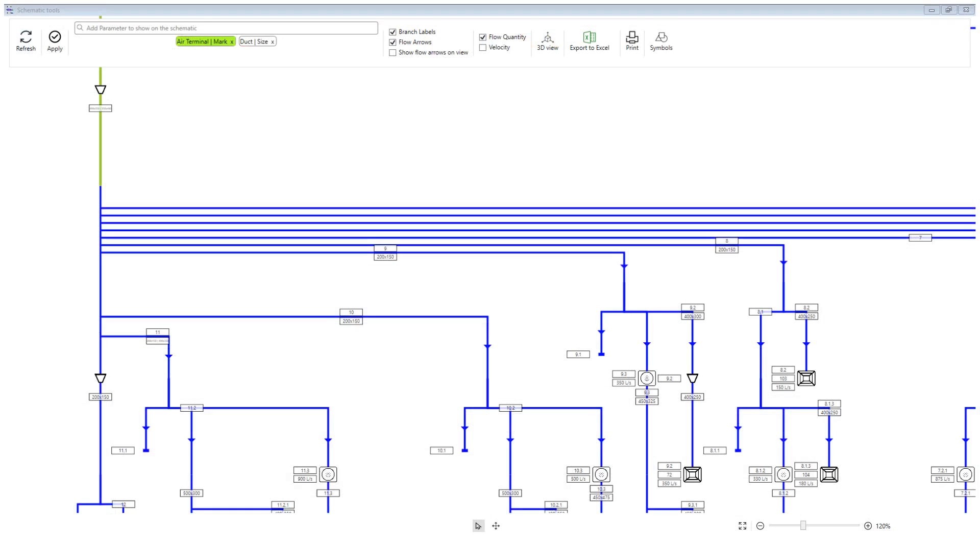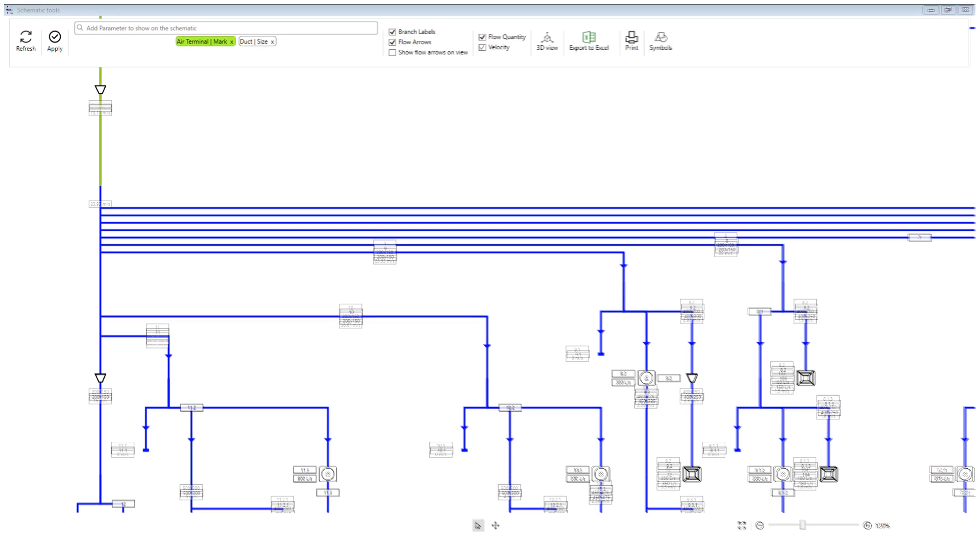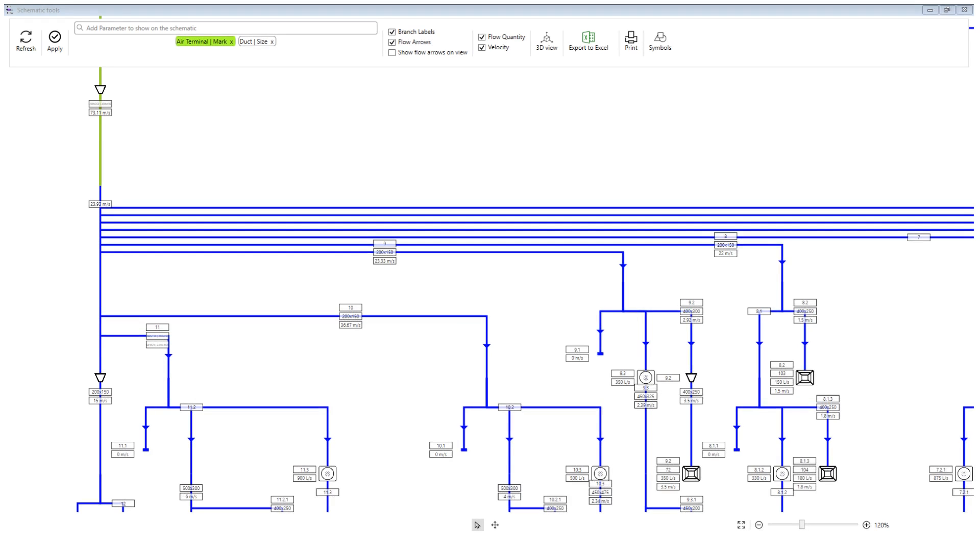By clicking on the flow quantity checkbox, the app will read the flow quantities from the model and show them on the schematics. The app will add up the flow quantities through the duct system and shows the quantities on each mechanical equipment and each branch. You can also click on the velocity checkbox to see the calculated velocity for the ductwork.